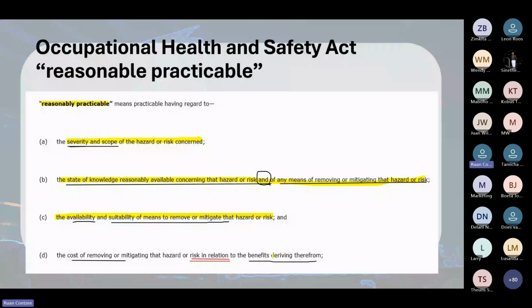But we're not done, because reasonably practicable also says you have to take into consideration the cost of removing or mitigating the hazard or risk. This is where most electricians stop reading, saying it's too expensive, so they won't apply that solution or incorporate that component. But the term expands to say you have to weigh the cost of removing or mitigating that risk or hazard against the benefits derived therefrom. So a 100 Rand switch compared to preventing someone from being electrocuted, or incurring a design change that might cost 50 or 60,000 Rand - what are the benefits derived from it?